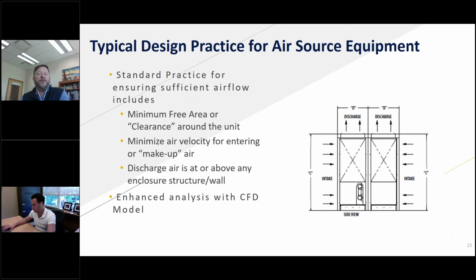We need to use those for an air-cooled chiller. We also need to use those for an air source heat pump. And especially with traditional practice, if we're looking at a single unit, that is very easy to accommodate. If we start getting into a situation where, let's say, it's in a pit or in an enclosure and the discharge is not at the top of the enclosure, well, then we can't use those general rules of thumb. We have to really start looking at it more in depth.